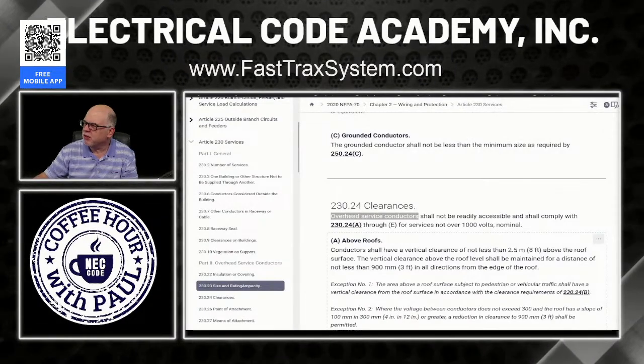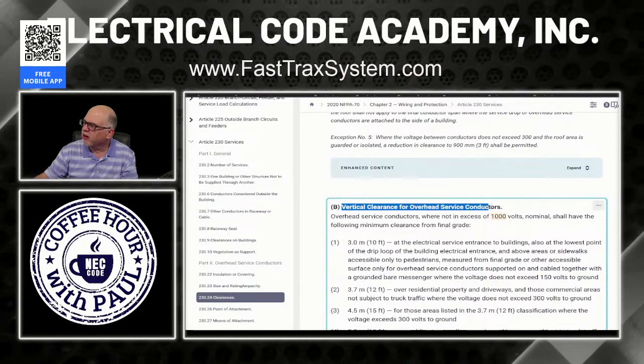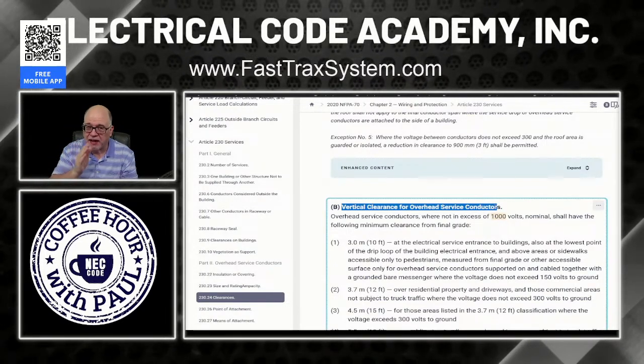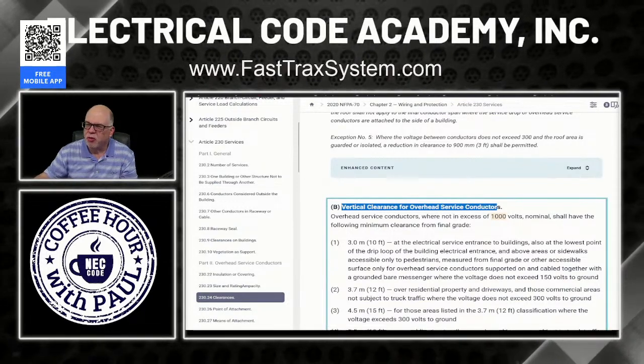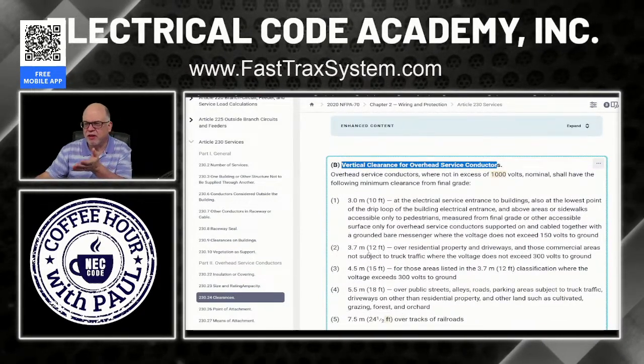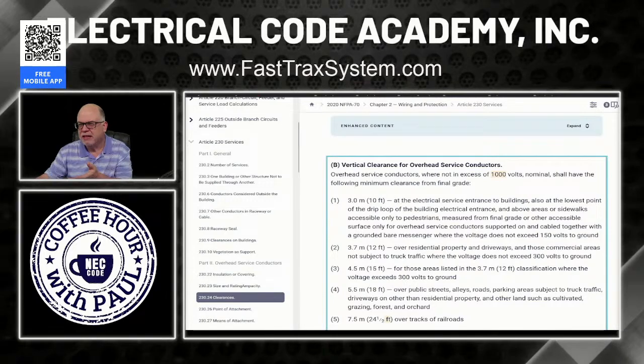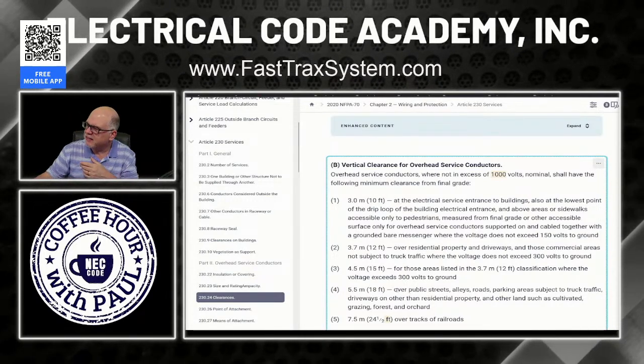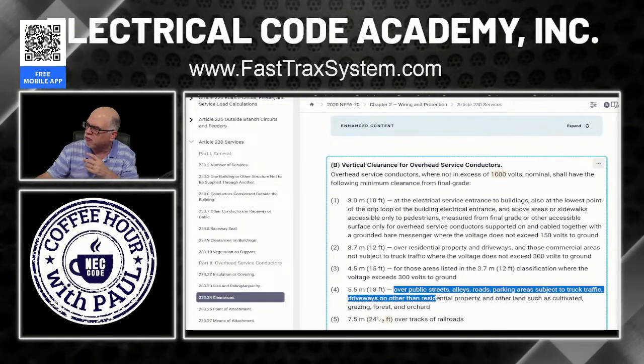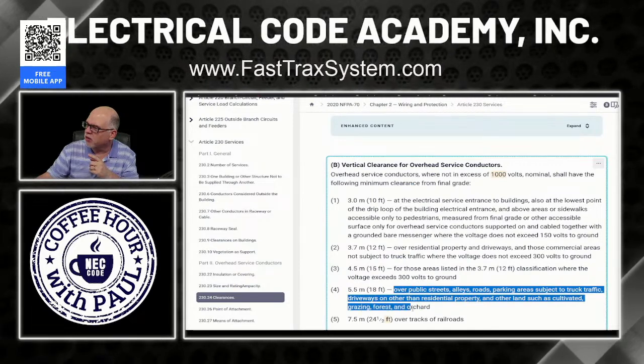So here we are, and we're going to be looking at B. So here it is. Notice it also says vertical clearance of what? Overhead service conductors, not service drops. And that's a defined term in Article 100. So now it's assuming this is an overhead service conductor, then you have the clearances right here. And we chose, in this case, 18 feet. Why? Because this looks like a commercial building and it's a non-residential driveway. So 18 feet for public streets, alleys, roads, parking areas subject to truck traffic, driveways other than residential properties, and other land such as cultivated, grazing, forests, and orchard.